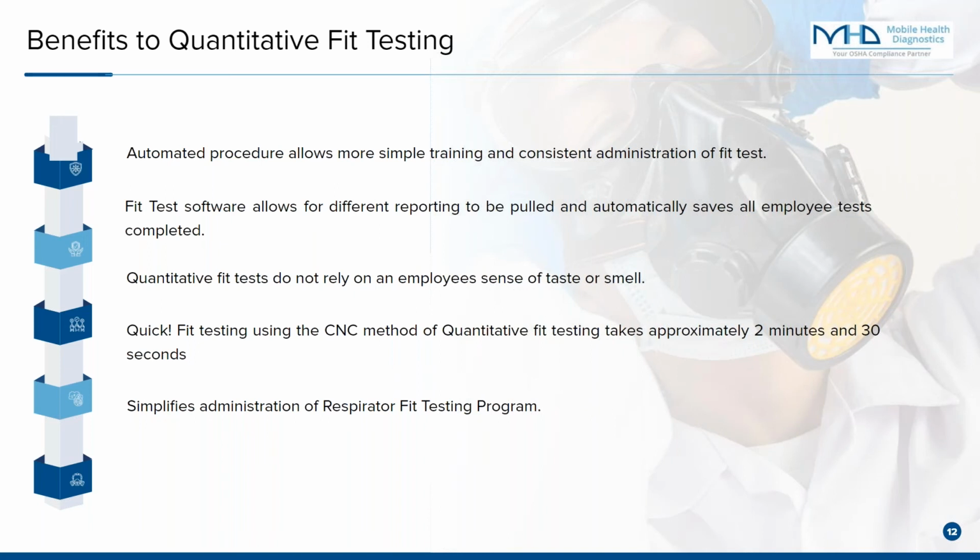Whereas with qualitative fit testing, there are some intricacies. Once you do it a few times, it doesn't change a whole lot, but the number of times that the nebulizer needs to be squeezed can vary from test to test, based on the person being given the fit test and their response to the beginning portion that I went over a second ago. So it can vary from test to test.